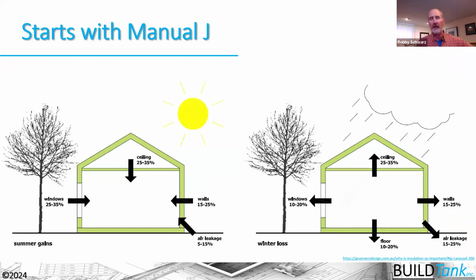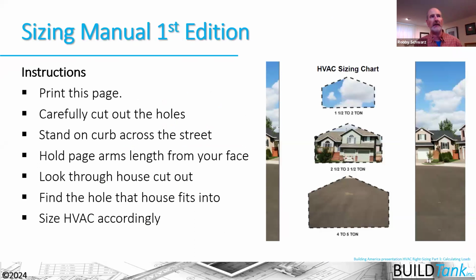So we begin with our Manual J. Manual J, again, is trying to determine the heating and cooling loads in the heating season and in the summer cooling seasons. And we used to do that in a kind of haphazard way, with just broad assumptions. So this was a device that people created where you walked across the street from a house and you put this picture up, and you could tell if it was a 1-ton or a 4 or 5-ton house, if that house fit within the drawing here.